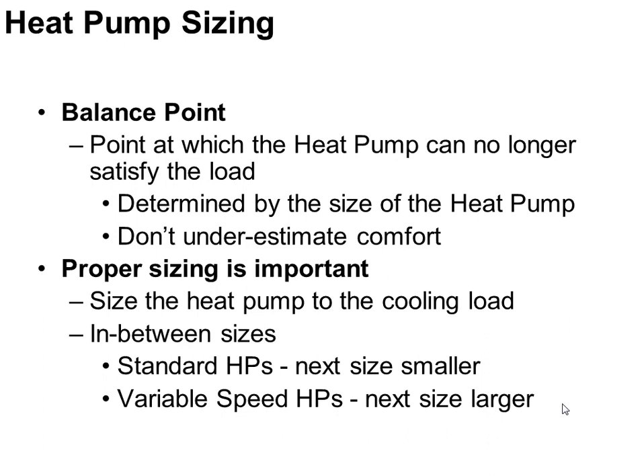However, with these variable speed heat pumps, because we can ramp them down to avoid having too much capacity, instead of telling you to size the heat pump for the cooling mode or even round down, we're going to tell you to round up to the next larger size. So if you had a 33,000 BTU cooling load, we'd say at least put a 3-ton heat pump in, maybe even the 4-ton heat pump. And we'll look at that here in a minute.